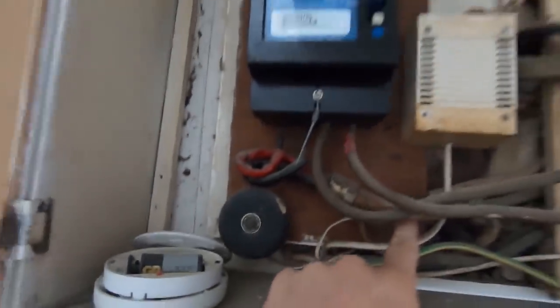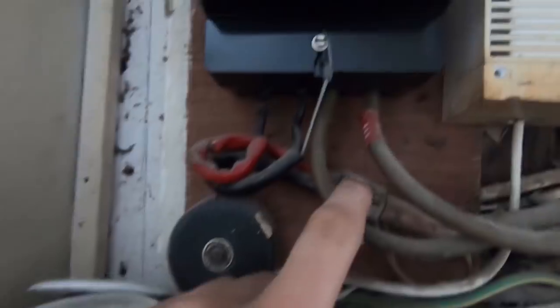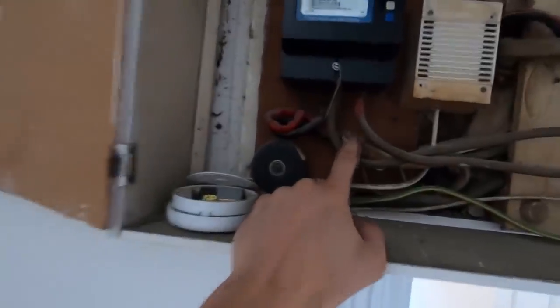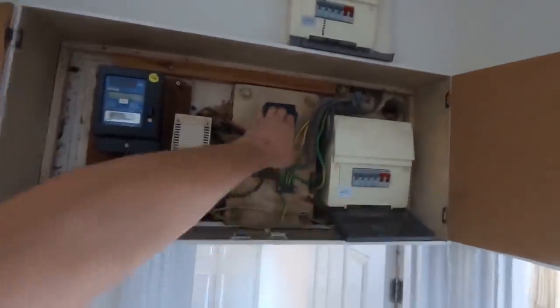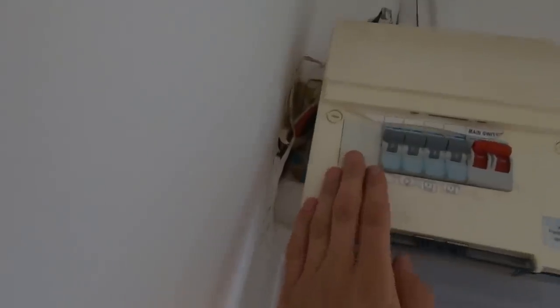We've got this thing here again. We've seen this a couple of times in the past, but you've got these little 6mm tails. You've got an MI cable and it's just a 6mm, so I've got to find where that is - I've got to see what size fuse that's on downstairs. I've got a feeling you're just going to have to take both those boards, pull them out, get rid of all of this completely and just put a nice fresh board in. Another fuse board - yeehaw! Yeah, we're here for a little bit I think.